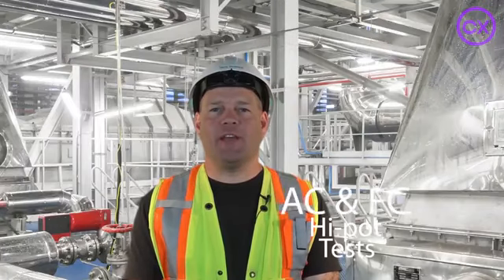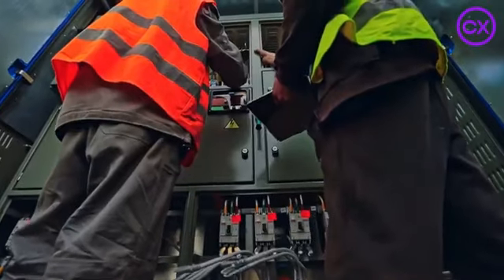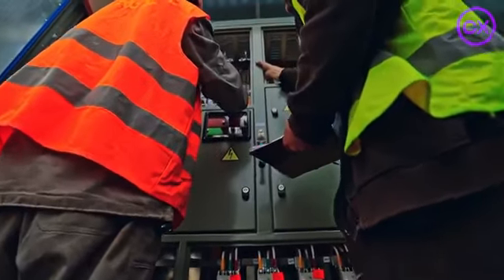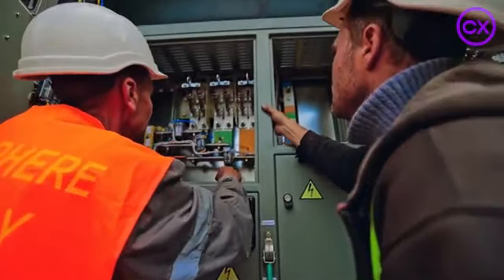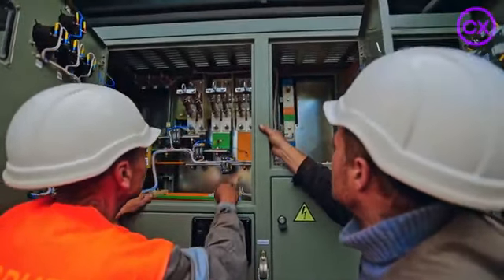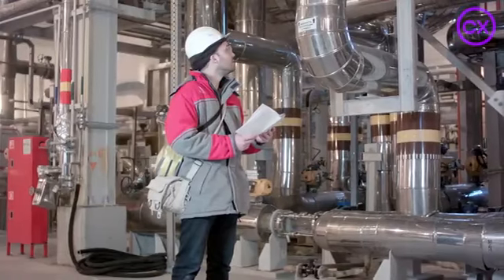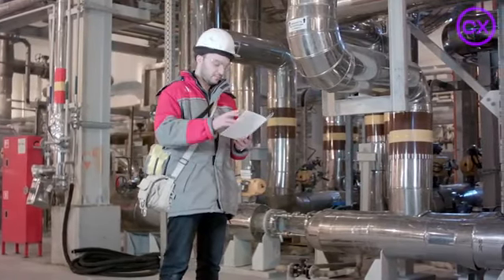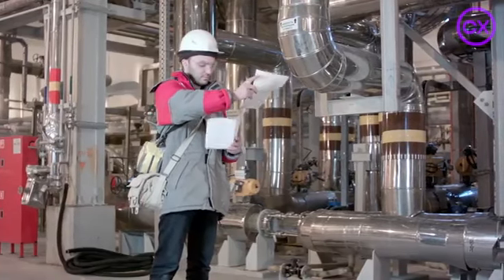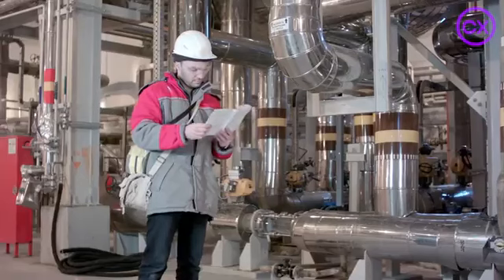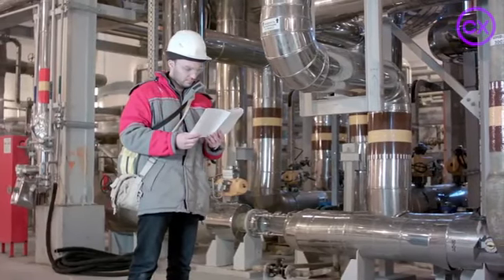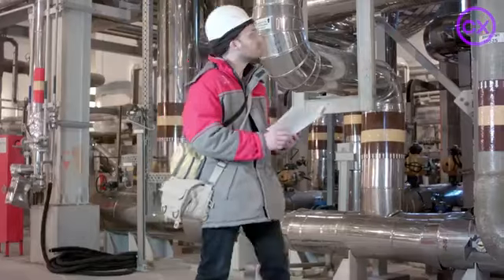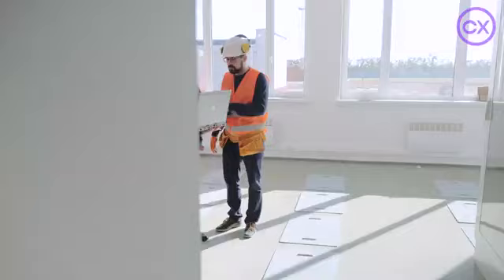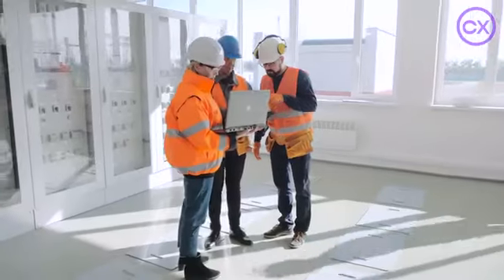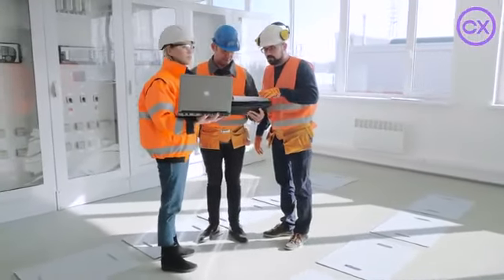AC and DC high pot tests. This measures the ability of a dielectric to withstand rated and transient voltage. Battery discharge tests. This confirms how many hours of rated voltage and current can be supplied during charge and discharge cycles. Pre-commissioning is complete once you've completed all your checklists and verified that each piece of equipment meets the technical requirements of the project. Pre-commissioning tests equipment as standalone items. Tests during pre-commissioning don't necessarily operate the equipment as a system yet. Each piece of equipment is individually confirmed to be ready for further commissioning tests.